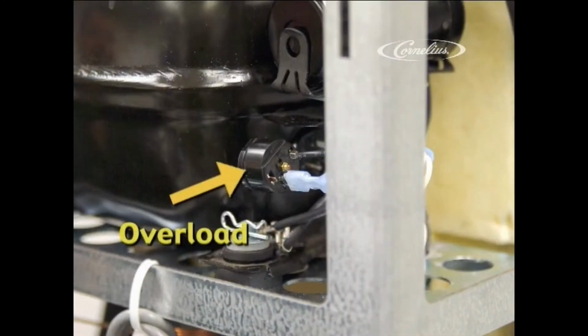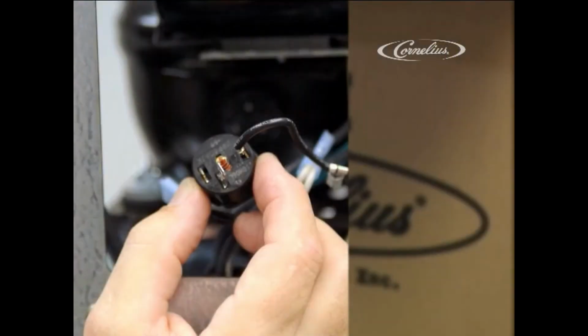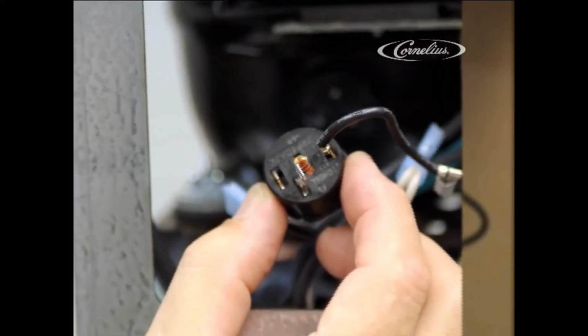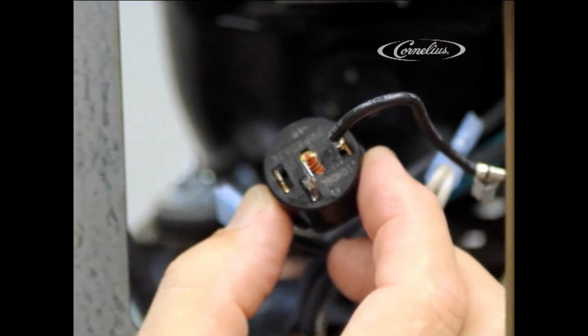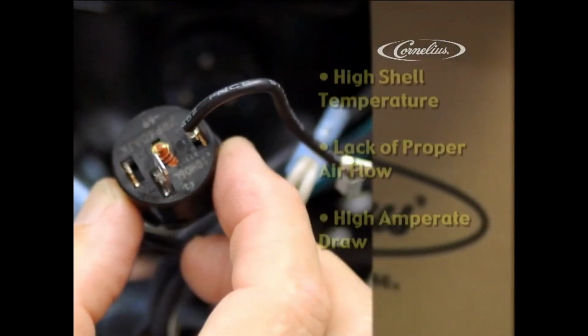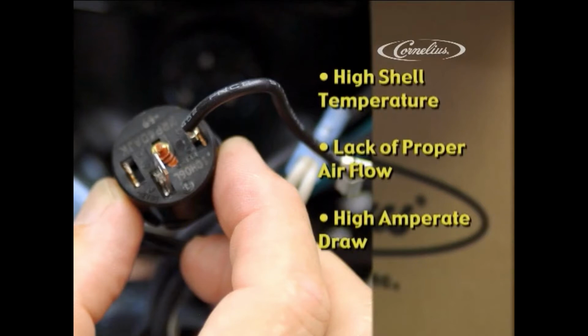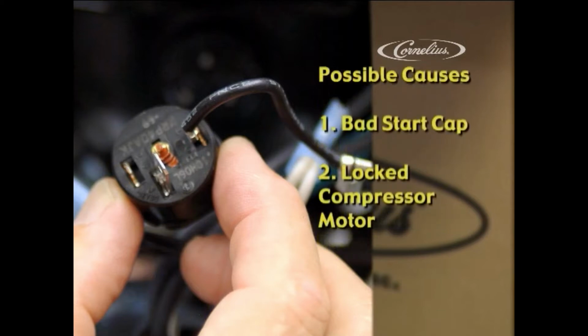This is a snap-action bimetal motor overload protector. When the bimetal discs, usually steel and copper, reach a certain temperature, they snap back, opening the circuit. When cooled, they assume the closed contact position. The temperature can be caused by a high compressor shell temperature, lack of proper airflow to the unit, or a high amperage draw from the compressor motor itself. A bad start cap or locked compressor motor can cause this to happen.